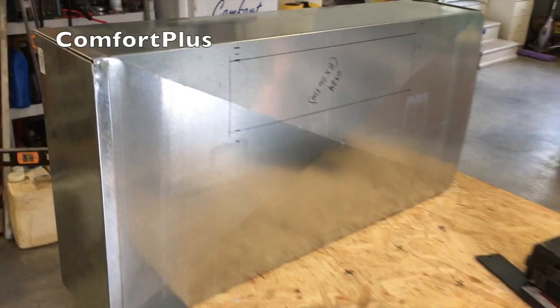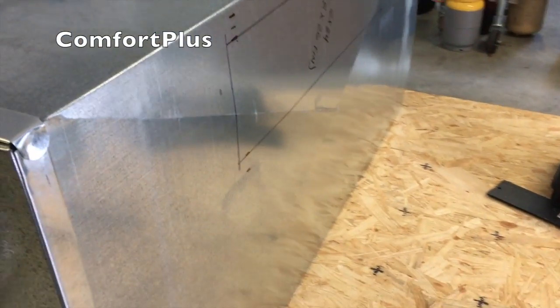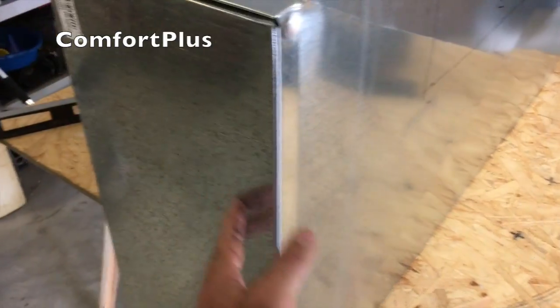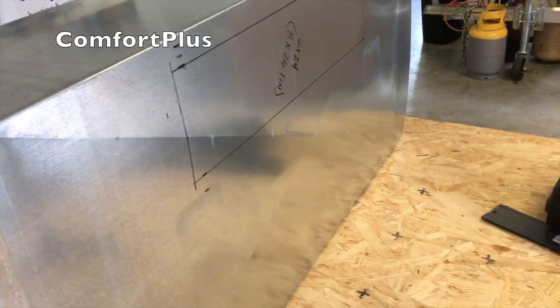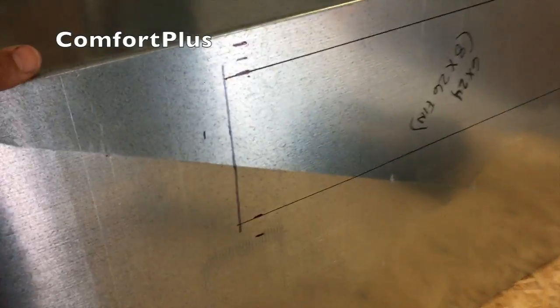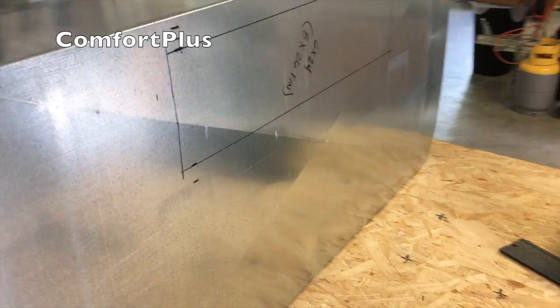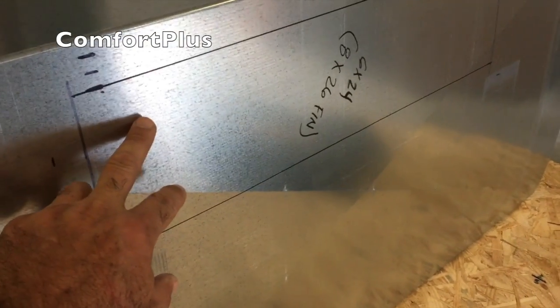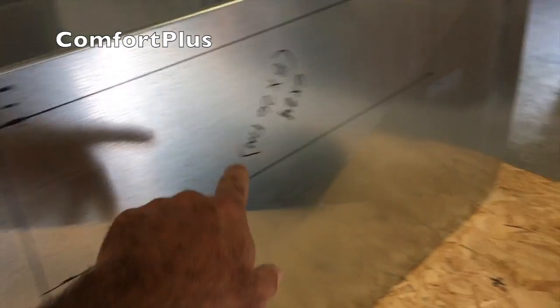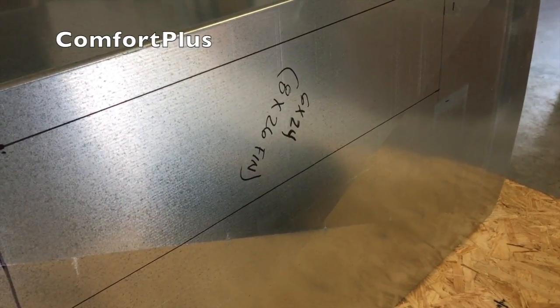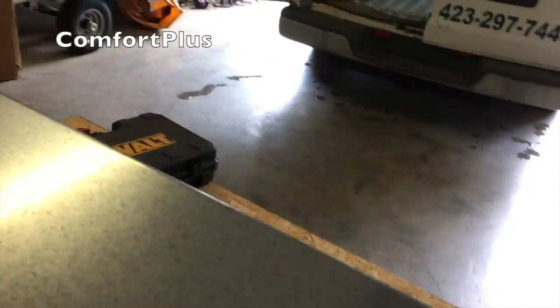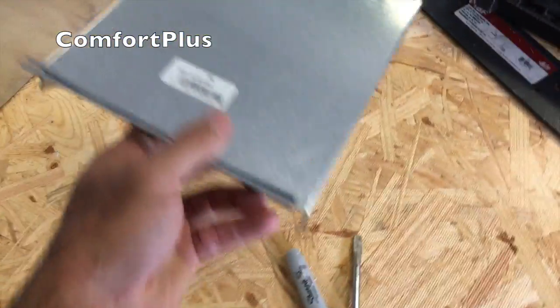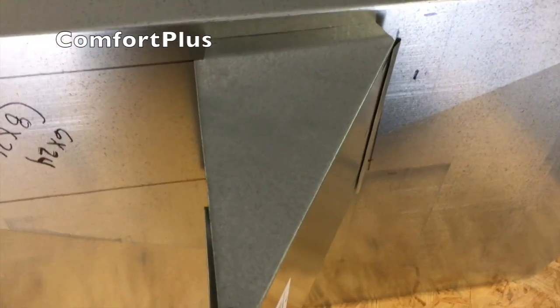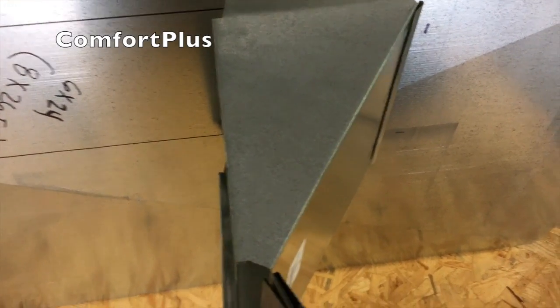Okay, here we have a piece of just stock 6-inch by 24-inch trunk duct. Bought a factory end cap and stuck on it. What I'm going to do is, it'll be standing upright down in the crawl space, about like what you see here. I am going to connect an 8x20 duct up here, which I'm making the actual opening for 8x26 duct, because what I will do is take one of these reducers and put it on my 8x20 duct to allow the air to be able to turn into this branch duct easily.